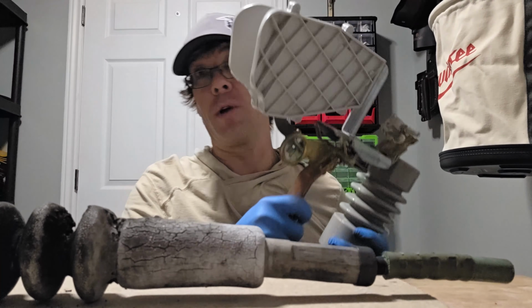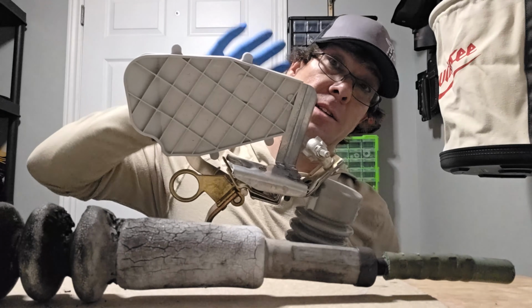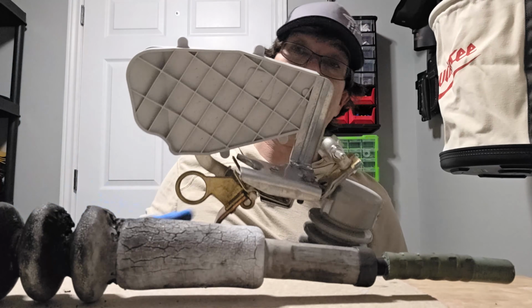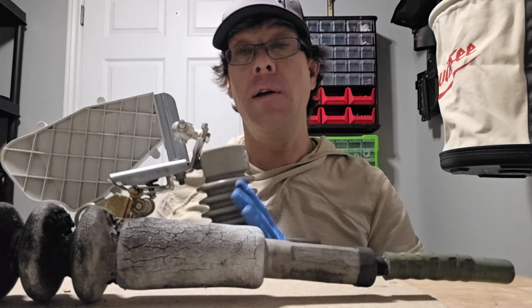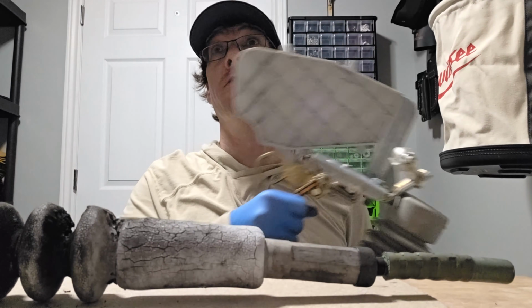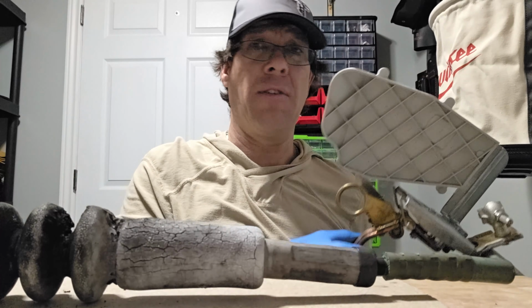But this is what we put back up, load break. So the cutouts that were initially there did not have this load break capability. If they had, I would have been able to open all 3 from the ground. The only way I could have opened them once it was on fire would have been to climb and put a load buster on it, which I'm definitely not going to do.